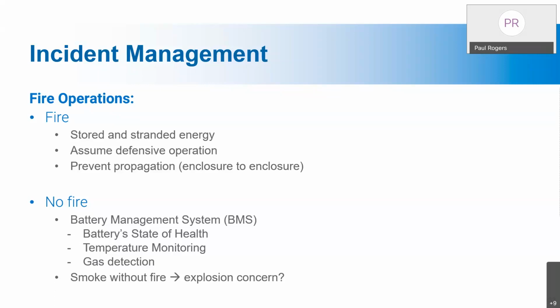Is that trending temperature being monitored through the BMS continuing to rise? If it is, that's a concern for the fire service, even though they may not see anything on the outside. So they may need to get that information out of the battery management system, which is instrumental.